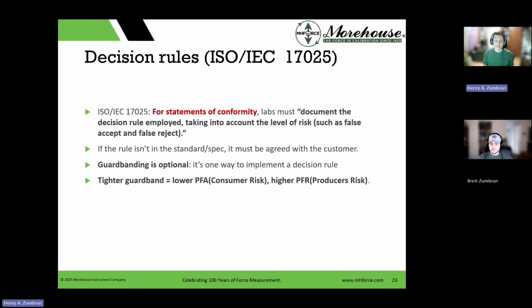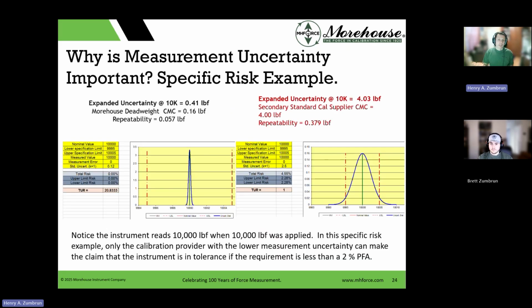Just know this: a tighter guard band means lower consumer risk, less chance of saying something's good when it's actually bad. But you have higher producer's risk, where we're going to say more instruments are bad when they're actually good, because we're guarding really, really high amounts. I'm going to show you graphs with this. So, expanded uncertainty in our dead weight machine, going back to the load cell example we did eons ago, we had these two uncertainties, 4.03 and 0.41. The dead weight machine has the lower uncertainty.